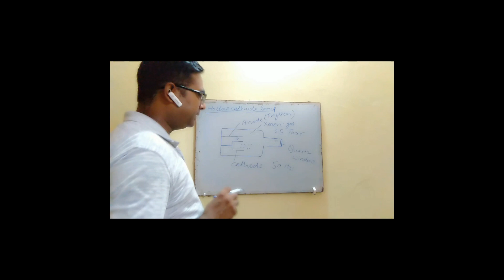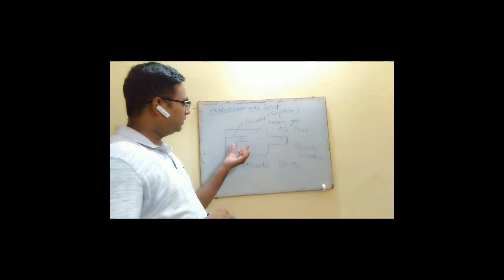So the line spectrum emitted by the hollow cathode lamp is similar to that which has to be absorbed by the sample present in the flame. The cathode of the hollow cathode lamp is made up of the material that has to be analyzed in the sample, and therefore it emits the line spectrum which will be absorbed by the metal present in the sample. So we have to use a separate hollow cathode lamp for each metal, and this is the drawback of atomic absorption spectroscopy, that in the analysis of different metals we have to use different hollow cathode lamps.